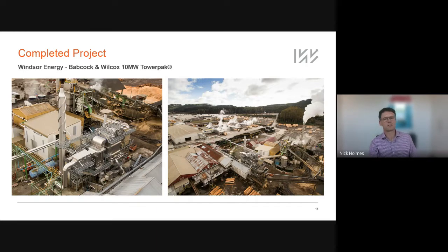Anything of significance that we learned through this one? Probably we took on a commitment with very high moisture fuel. The boiler has accommodated that very well, but we did learn that the emission control system was right at its limits. We did get away with a cyclone system, a multi-cyclone. I think next time around we would probably have to go to an ESP or a more sophisticated baghouse to get those emission levels a little bit lower. Certainly Australia has probably lower limits than this site had.